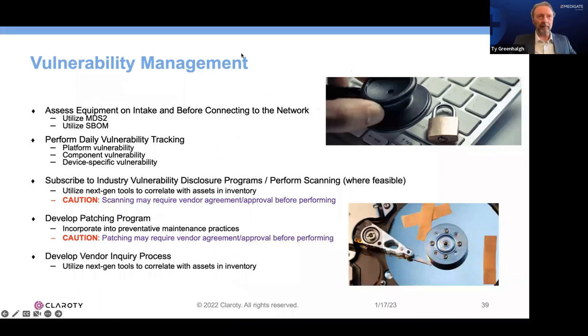Vulnerability management, same thing. We talked about IT-based vulnerability management systems not being able to scan medical devices because it's very aggressive. They go in and say, like when you put your laptop on a network, it says you need to upgrade your software, and then you go ahead and do it. The reason it knows that is it's querying your device. Medical devices aren't designed for that. So if you tried to query it like that, it might turn it off. And if that's attached to somebody, some medical device, an infusion pump or what have you, that's a bad thing. So they don't scan them, and there are a lot of devices out there just sitting on the network. They just let them on because I can't restrict medical devices from coming on the network or query them.